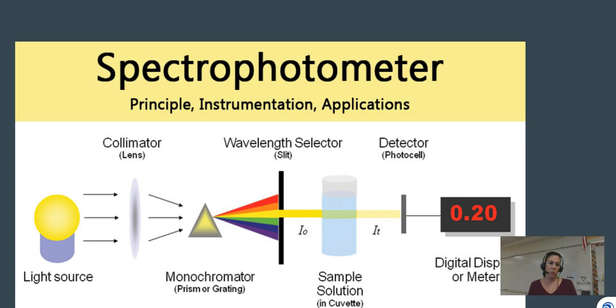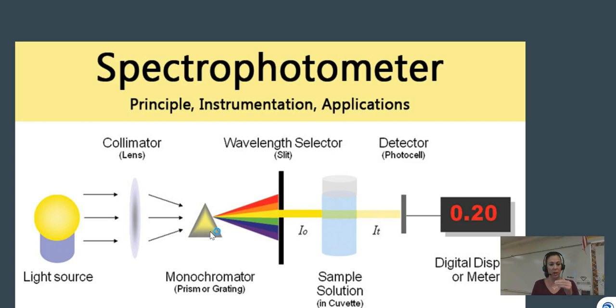Inside the machine, there is a light source whose light is condensed by a lens and then passes through a prism, which separates wavelengths into different colors. In this example, only the yellow wavelength is selected, and it goes through the sample in the cuvette. Whatever light passes through is detected by the spectrophotometer, which then calculates the absorption of that sample.